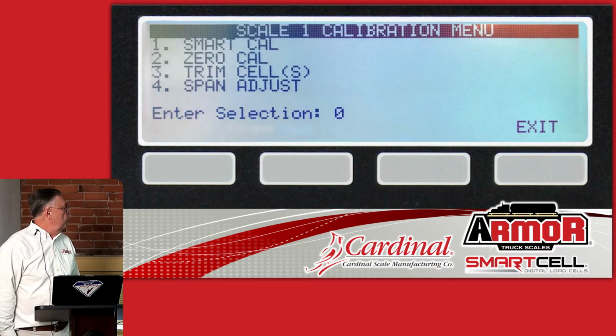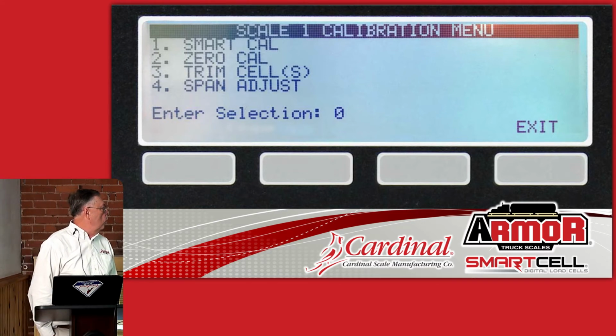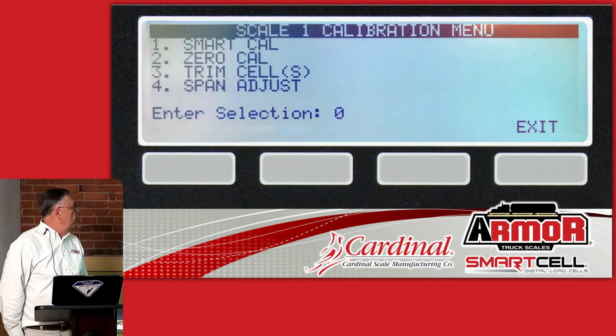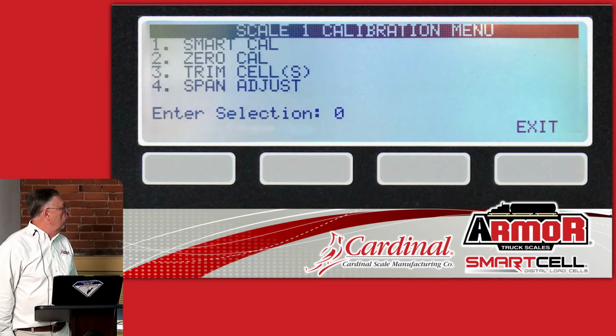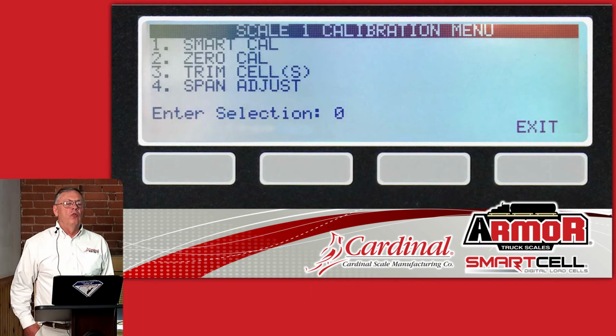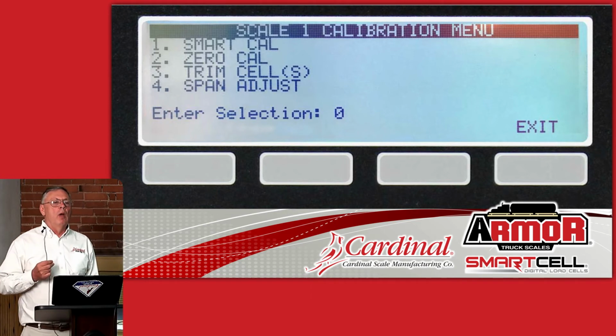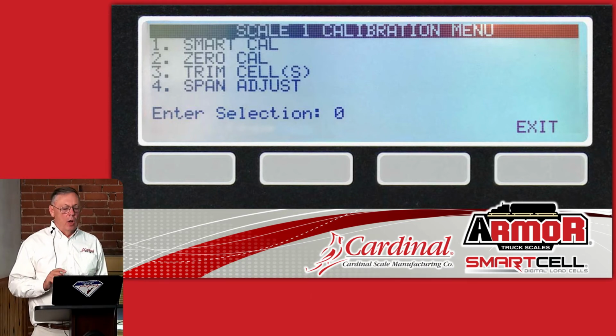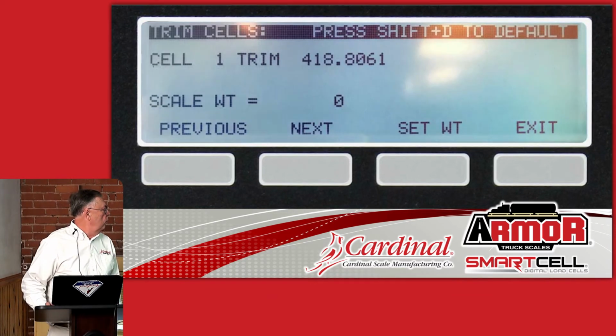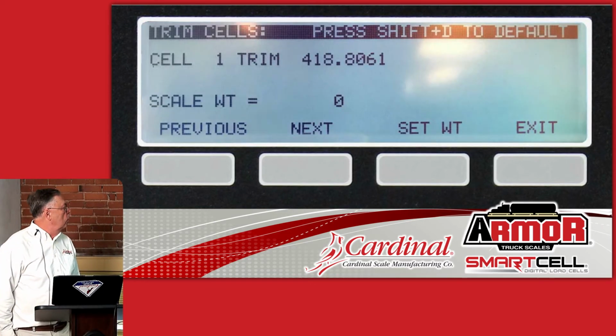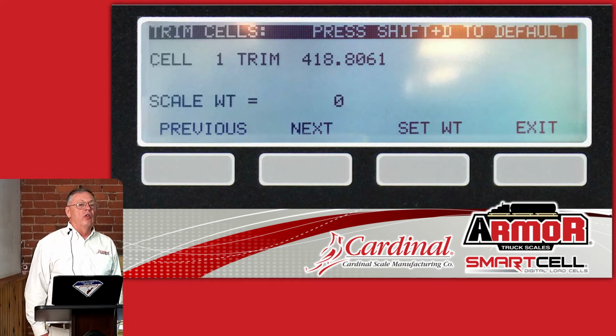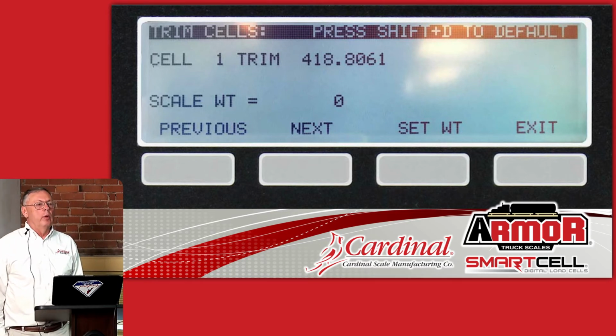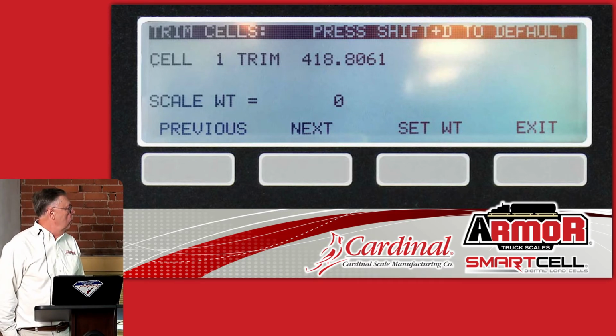Now, to make an adjustment to the output of a load cell or the output of a section, you would go to number 3 where it says trim cells. After you select number 3, it would come up and say which load cell do you want to adjust. And you enter your load cell number. And like here, I've entered load cell number 1. I want to make a trim adjustment. The scale weight there is the actual live scale weight that would normally be displayed on the screen, so you can tell where you're at.